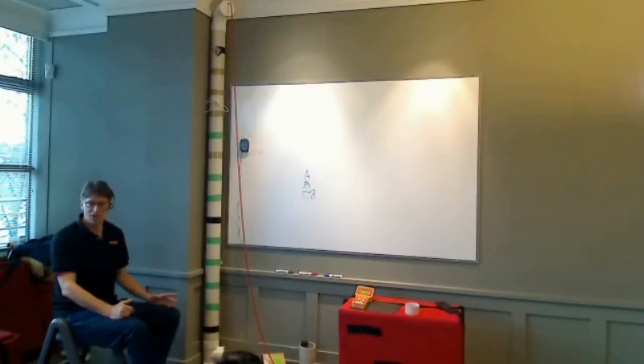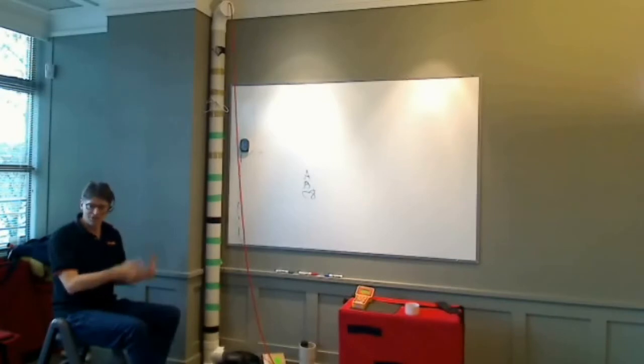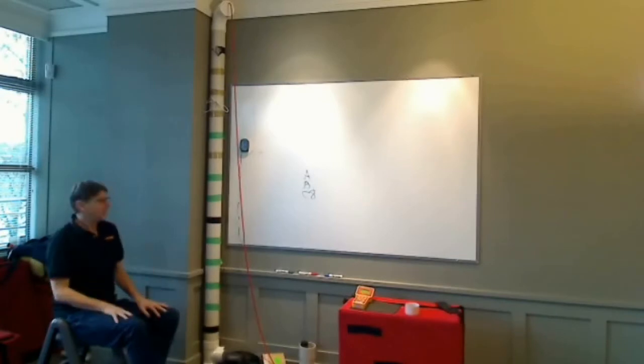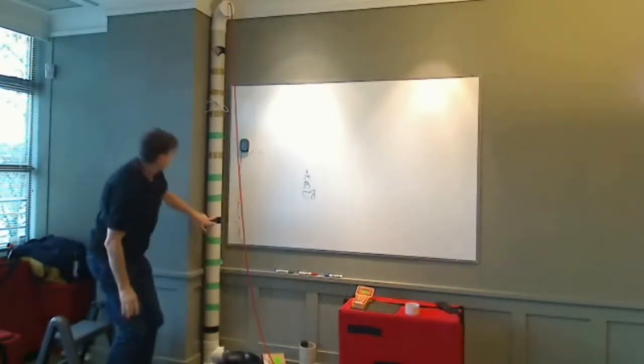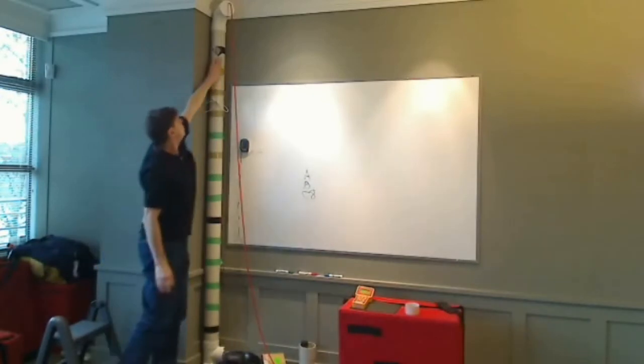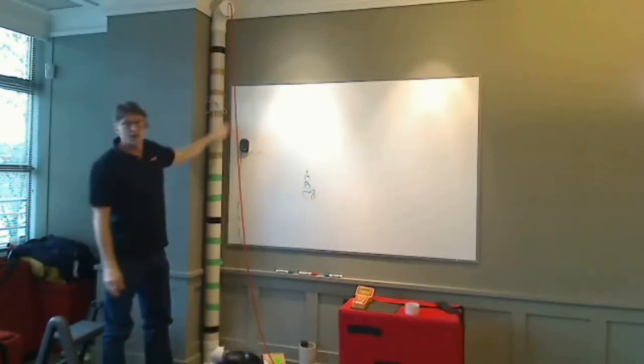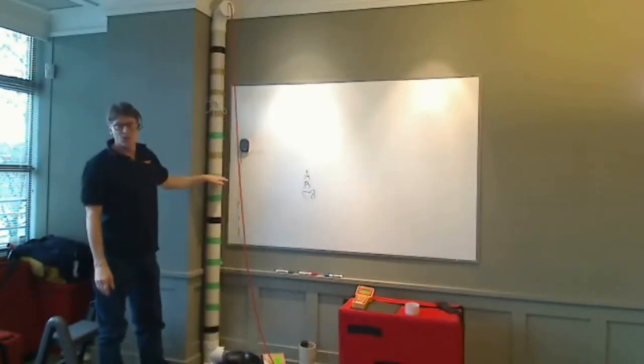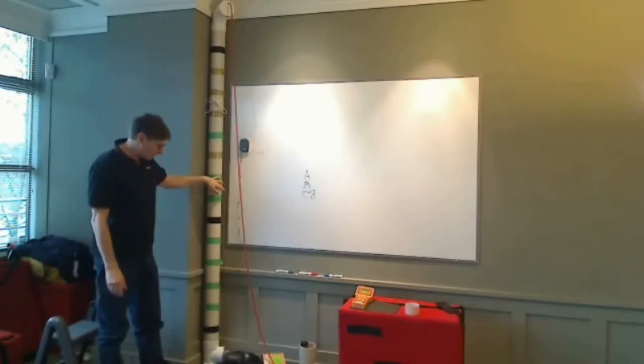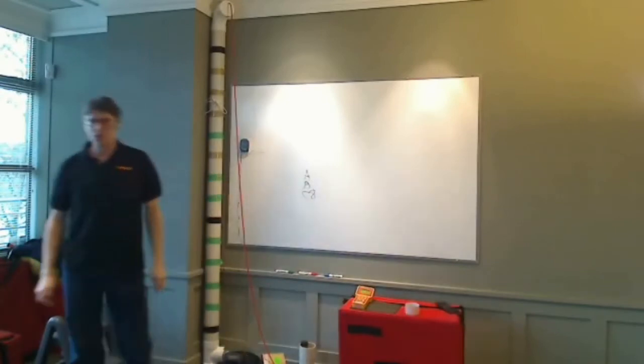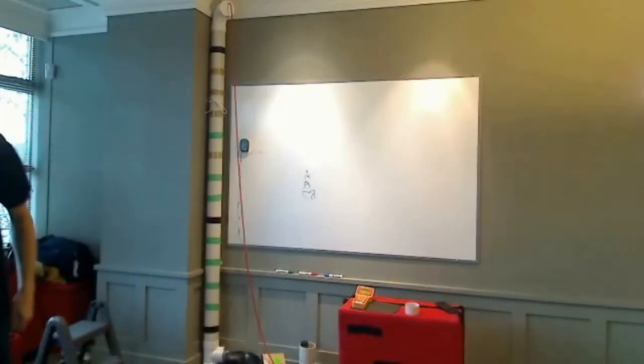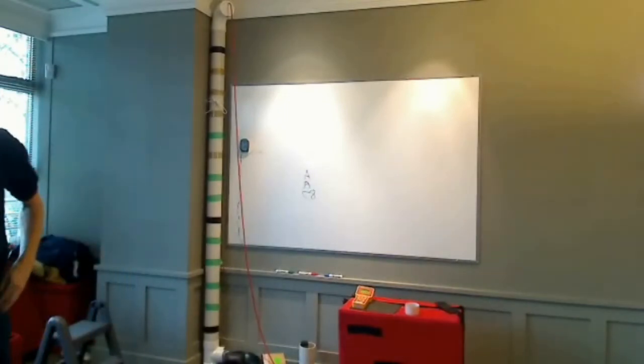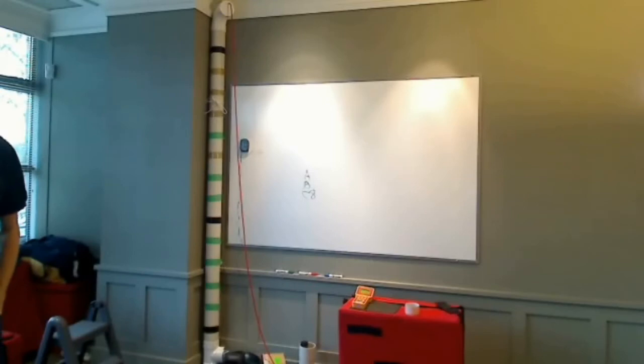If the dry ice was in the bag, you can get the effect of negative stack. You can also take pressure measurements all the way up and down the tube here and find out where the neutral pressure plane exists. It's my contention that people learn by doing and they learn by seeing, so this is a way that you can learn a lot about stack and have some fun with it as well.